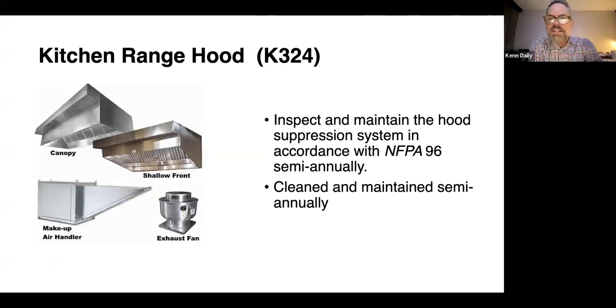And as I said earlier, that may be the same company, or it could be two different companies, but you're having somebody come in and clean your range hood, going from the exhaust fan all the way up through the canopy and through your roof, making sure that the metal itself is cleaned down to the metal. No less than every 6 months. So if you have a lot of deep frying or a lot of grease-laden vapors, there are buildings across the country that do it more frequently than every 6 months, but no less than every 6 months.